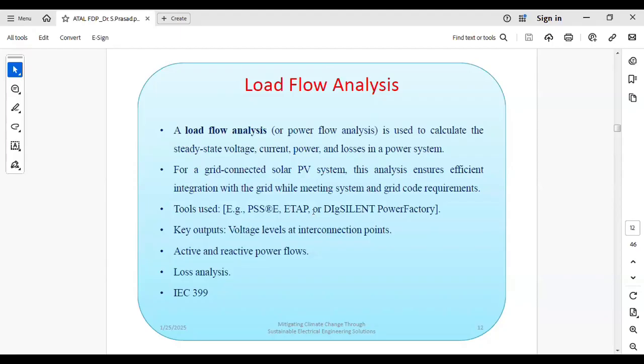in each analysis. So load flow analysis, as all of us know, is a steady state analysis performed to know the voltage, current, power, and losses in a system, and whether the voltage at all the buses is within limits or not. Suppose you are connecting the PV plant to the grid, at the PV plant end the voltage at all the buses should be within limits. And the transformer should not get overloaded. The IDT transformer, basically inverter based transformer, we are using. That should not get overloaded. What should be the rating specified? Those things can be verified by conducting the load flow analysis.